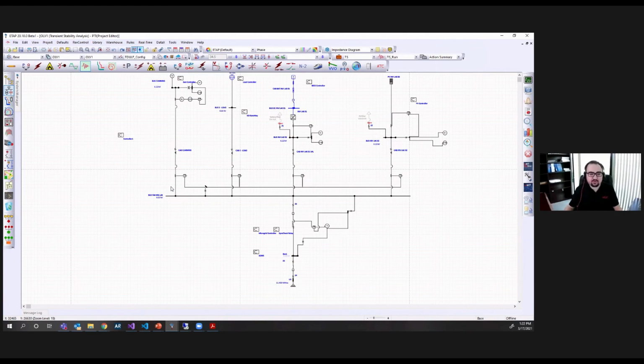For Microgrid controller purposes, for testing and tuning the Microgrid controller, because the Microgrid controller is a secondary level controller, its time step is around 1 second, 5 seconds, a couple of seconds. Both modules are good. We can use both of them. There is no basic preference to use transient stability or time domain load flow.